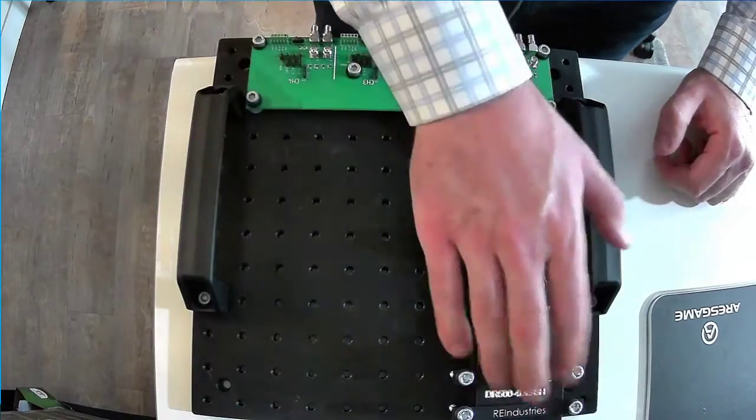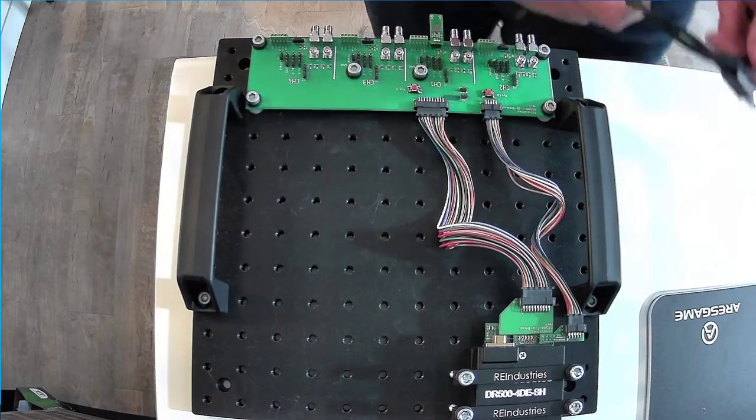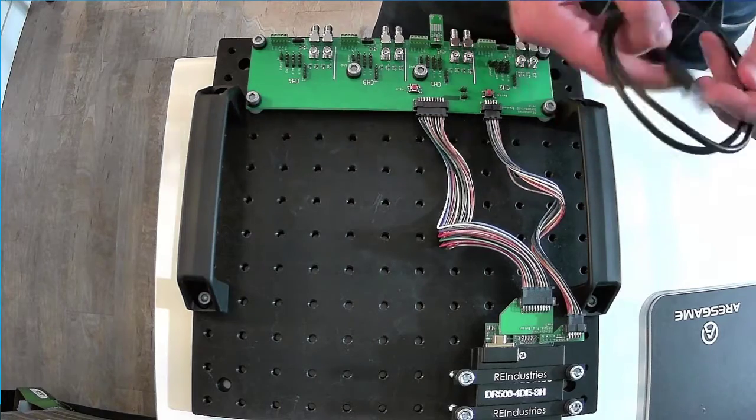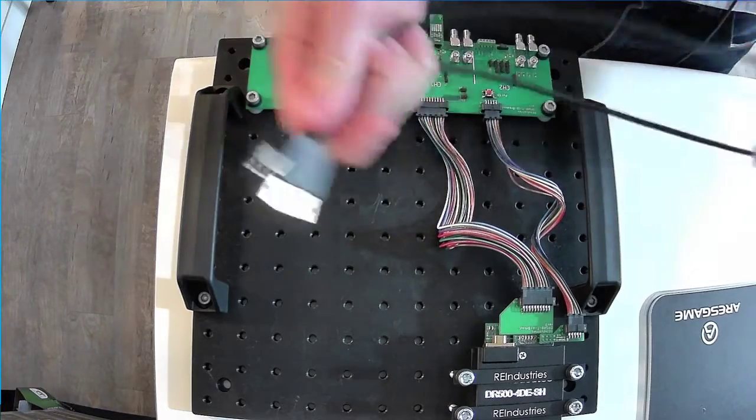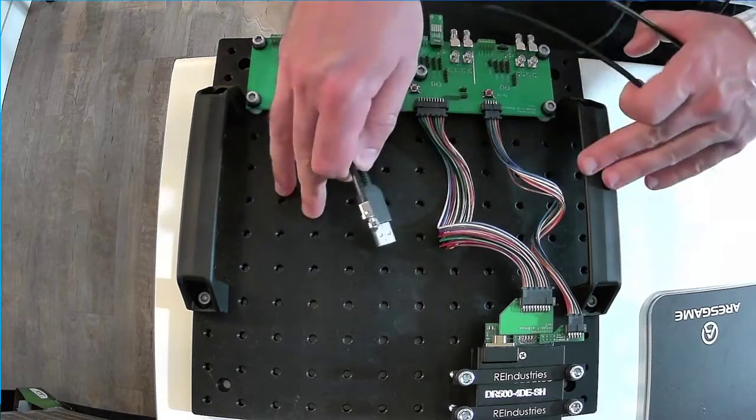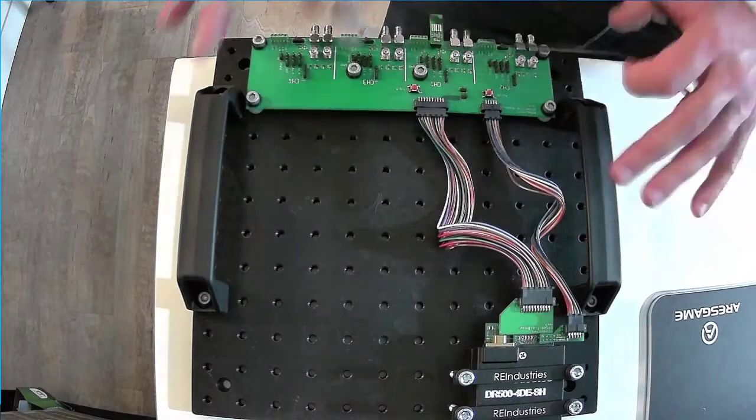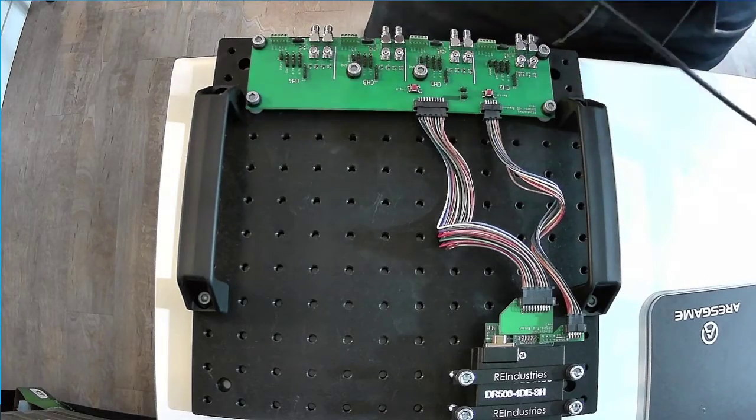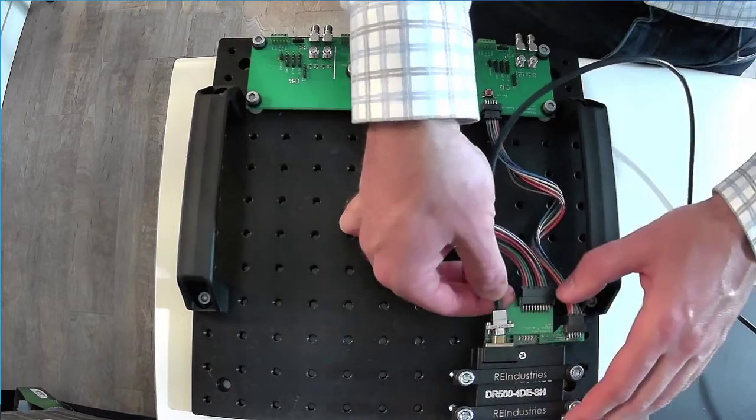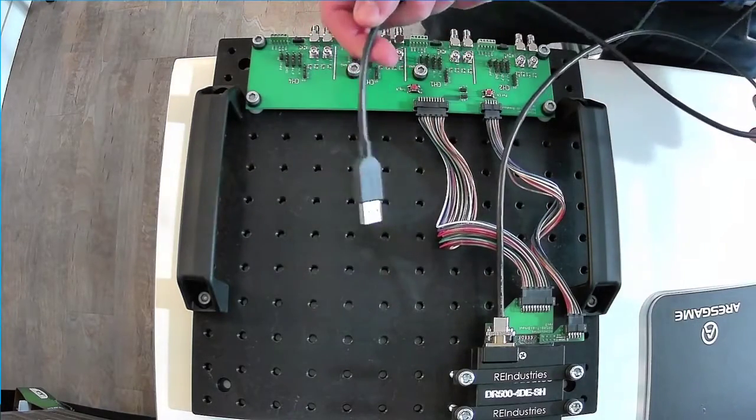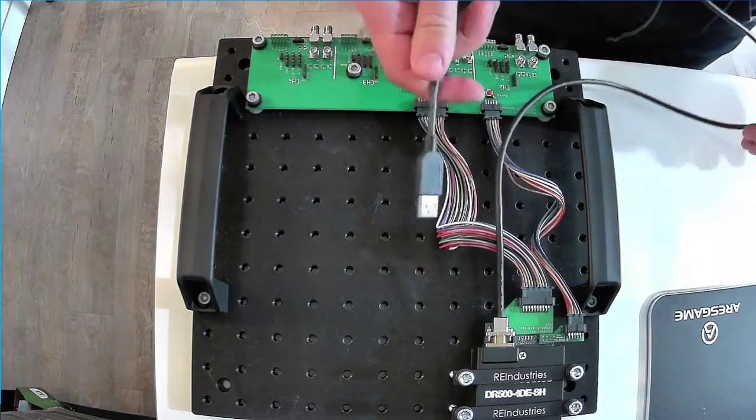And the interface to this is our standard ruggedized cable assembly here. It's a USB 2.0 link cable assembly. This comes with a data recorder. It doesn't come with this platform. The data recorder and cable are separate. But everything else you see comes with this platform. And so this plugs in the exact same way. The microd connector plugs in here, our standard microd interface, right on top of the analog breakout card here. And then this plugs into the workstation and connects up to our standard configuration software application.